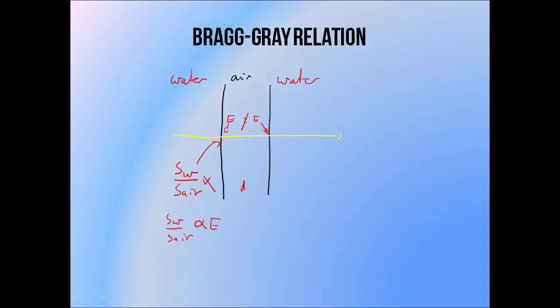Energy loss within the air volume depends on the distance travelled through the air volume — the bigger the distance, the greater the energy drop. But if we keep this distance very small relative to the range of the electrons, then any change of energy is very small as well, so we can assume that it's negligible. So one of the key Bragg-Gray conditions is that the chamber volume needs to be small relative to the range of secondary electrons produced by the beam we're using.